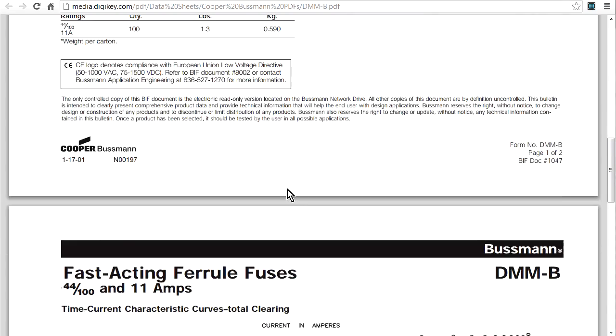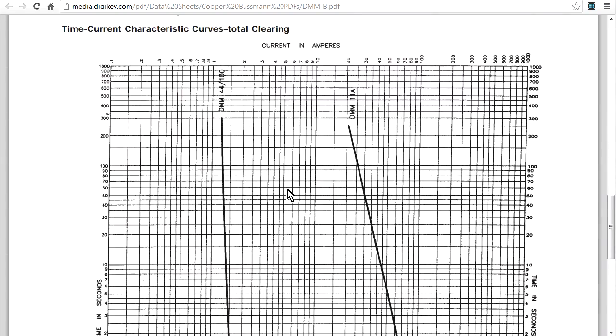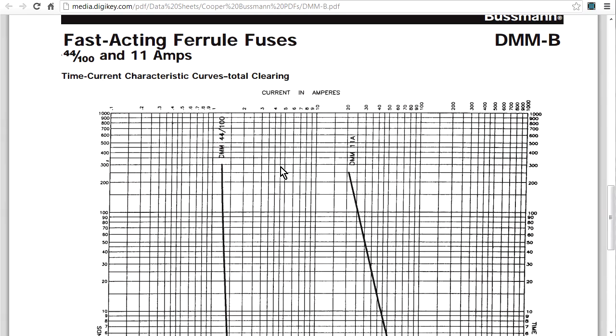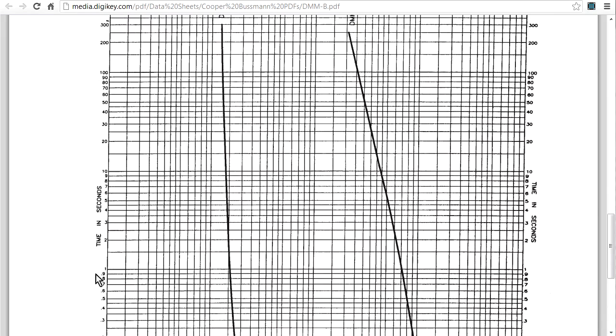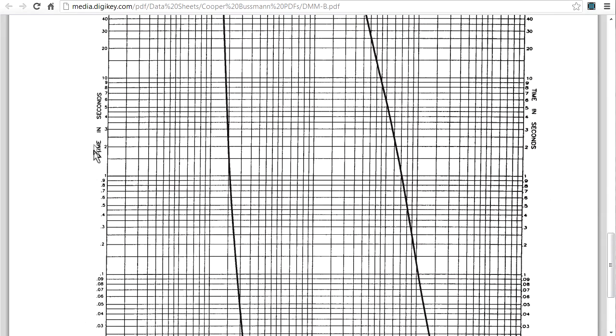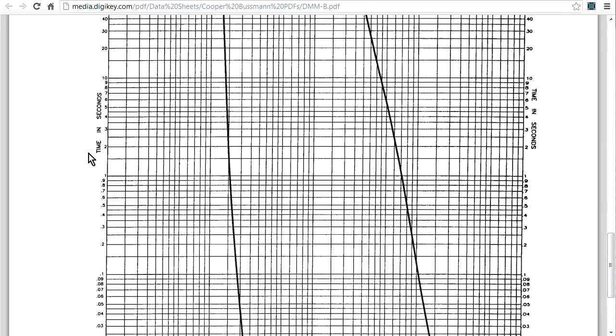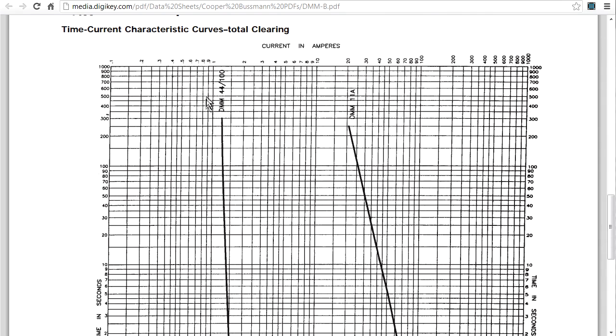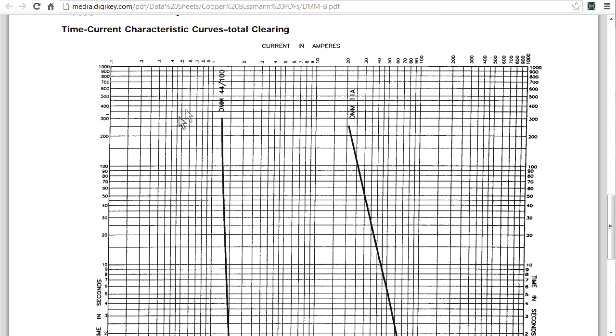So that's just a little heads up on these fuses. If it's rated to 440 milliamps, it's not going to blow at 440 milliamps. It's actually going to hold that current and never ever blow. It only blows when it's higher than that. And how much higher than that will determine how much time it takes. Now, if we go down here, we'll get some characteristic curves, and these will tell us.